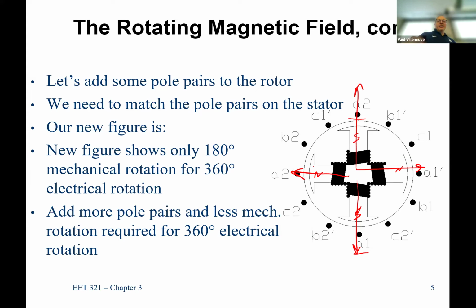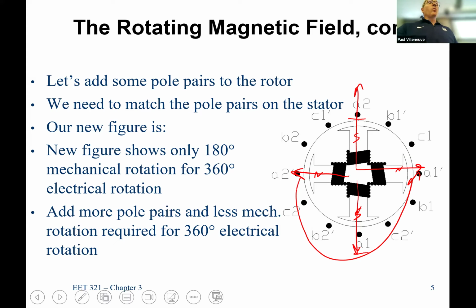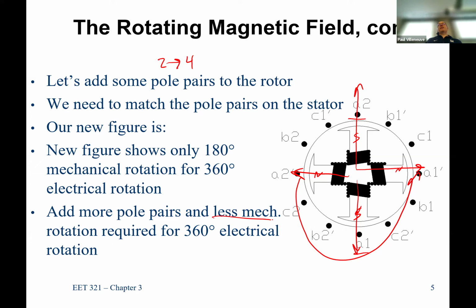I only have to rotate mechanically 180 degrees before I restart my magnetic field. So when I double the number of poles, going from 2 to 4, my currents are always rotating at 360 degrees, at whatever 60 hertz is equivalent to. But with more poles, I only have to rotate half as fast before I get back to another magnetic field from the currents flowing in the stator windings. So I need less, half as much.